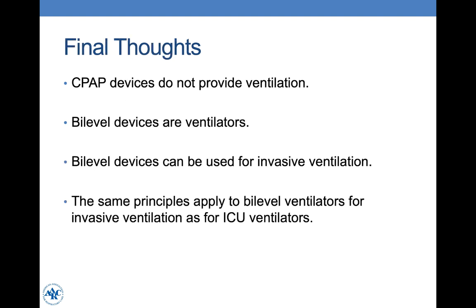In summary: CPAP devices do not provide ventilation, so it is not possible to use a CPAP designed for obstructive sleep apnea as an invasive ventilator. Bi-level devices are ventilators and can be used for invasive ventilation. The same principles that apply to ICU ventilators for invasive ventilation apply to bi-level ventilators as well.